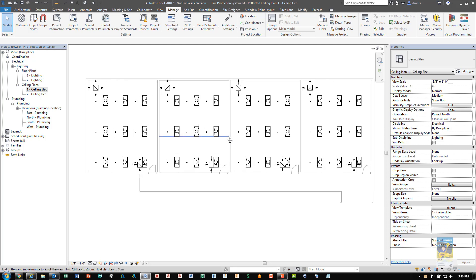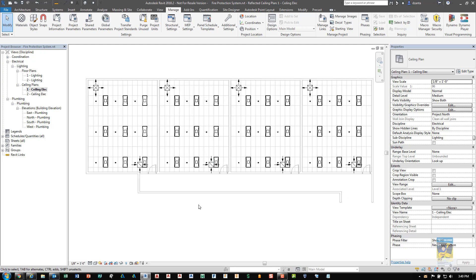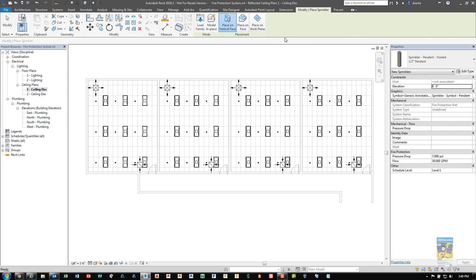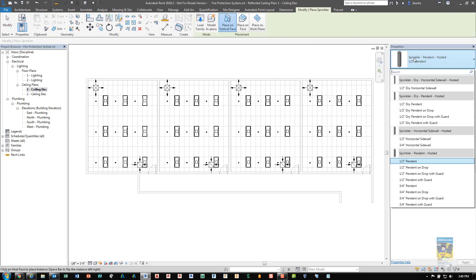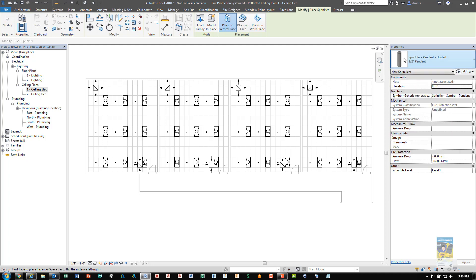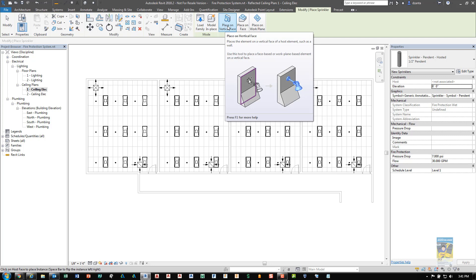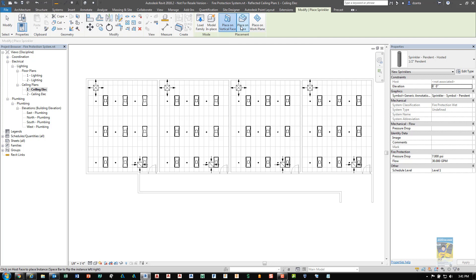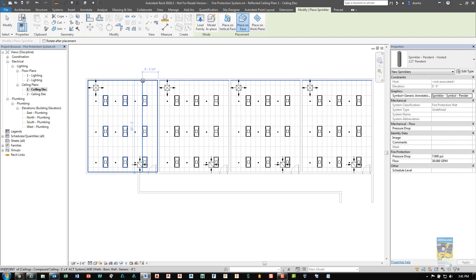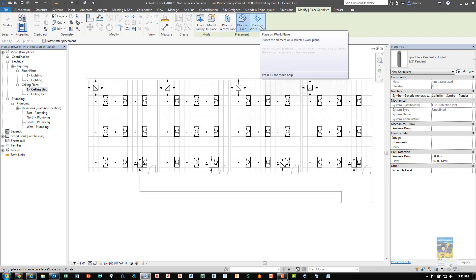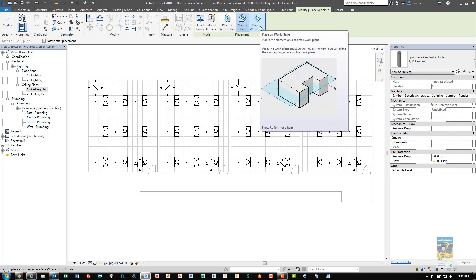The second step is to place the actual fire sprinkler heads where they need to go. So head over to the systems tab of the ribbon, head over to the electrical and you can see they have under plumbing and piping sprinkler command. When you use this command in the type selector, they've got a few for you to work with. Just pick the one that you want to work with. Make sure in the contextual tab of the ribbon, you are specifying how you are placing it. So in this instance, you wouldn't place it on a vertical face unless the sprinkler head is designed to be placed on, say, a wall and it shoots out towards the space. Most people will choose place on face and they'll touch the face of the ceiling and that way the sprinkler head knows it's hosted by that ceiling. You can also choose to place it on a work plane if you have a work plane to work with.